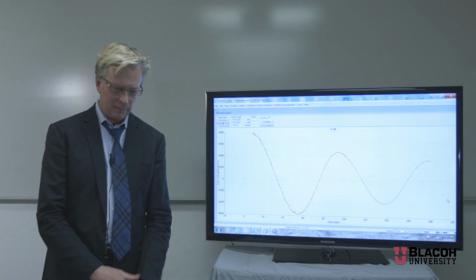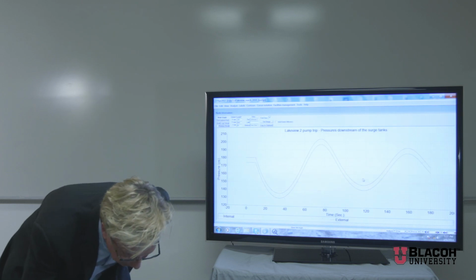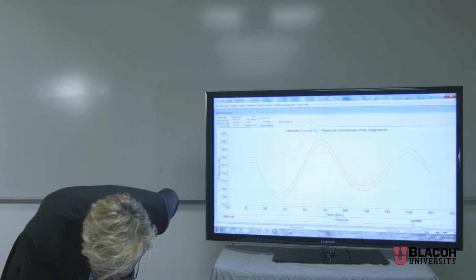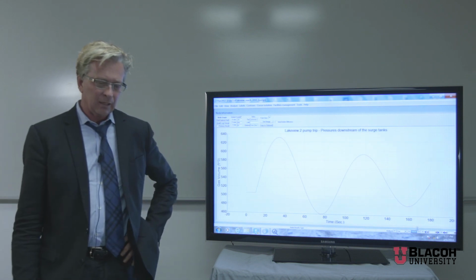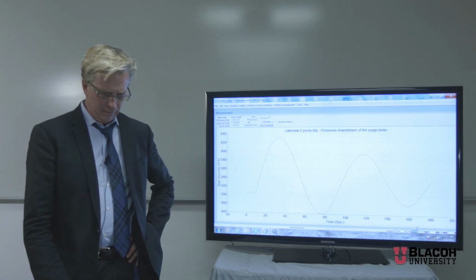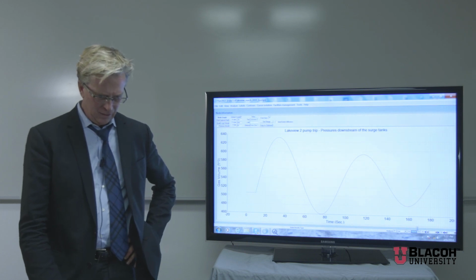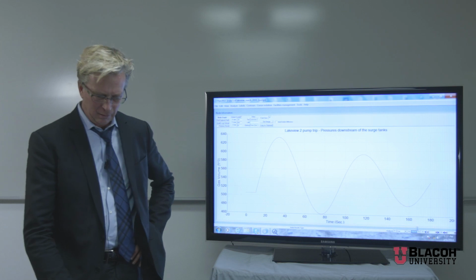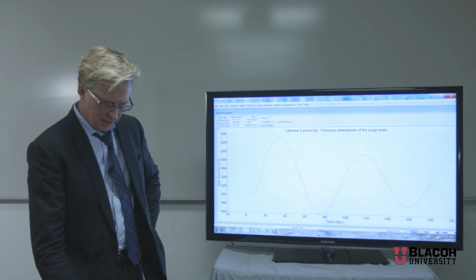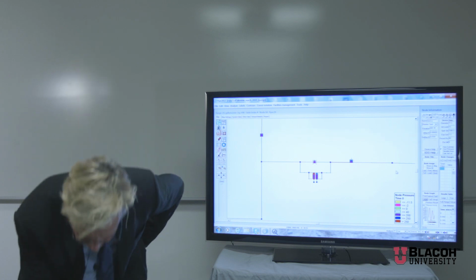Vessels gave energy, then accepted the energy back. Look at the pressure inside the vessel, and then we can also look at the volume change. Again, looking at the volume change, where we went from 510 cubic feet to almost 630 cubic feet, and then taking a step back, we look at the size of the vessel, which is 1,000 cubic feet, which gives us our safety factor, meaning that the vessel is not emptying completely. If it emptied completely, that bladder that I showed you is going to hit the outlet of the grid. Keep hitting the outlet of the grid, and you run the risk of destroying the bladder.